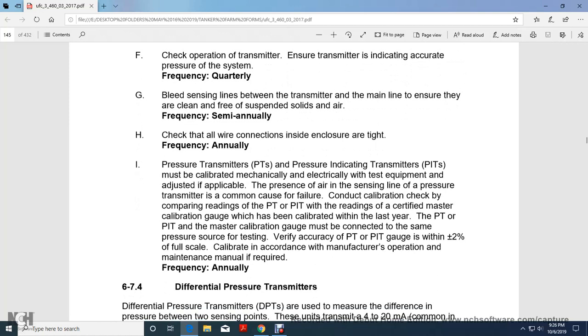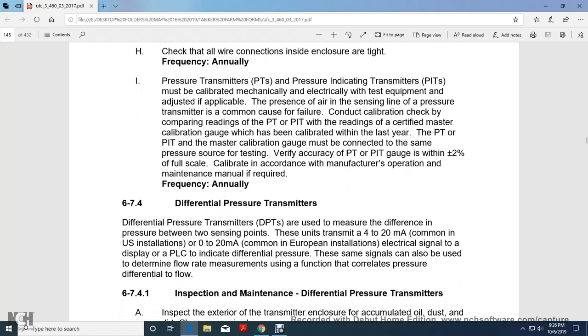Pressure transmitters and pressure indicating transmitters must be calibrated, mechanically and electrically tested, and adjusted as applicable. The presence of air in the sensing line is a common cause of failure. Conduct a calibration check by comparing the readings of the pressure transmitter and pressure indicating transmitter with the readings of a certified master calibration gauge, which has been calibrated within the last year. The master calibration gauge must be connected to the same pressure source for testing the accuracy of the pressure transmitter or pressure indicating transmitter, within plus or minus 2% of full scale calibration according to the manufacturer's operation and maintenance manual, if required, annually.